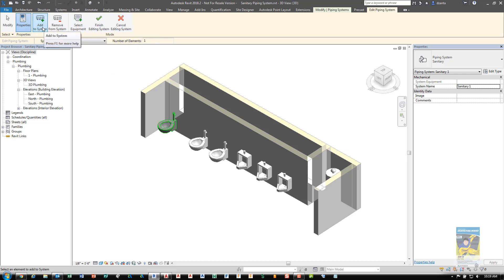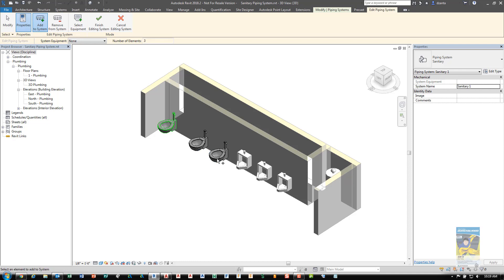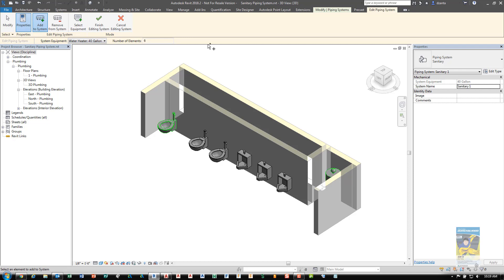By default, Add to System is turned on, letting you know I need to add other content. You can individually select other equipment or do a window crossing to tell the software these are all the components that make up the system. When you're finished, you need to tell the system what is the main equipment that it needs to tie back to. In this case, we'll choose the water heater. When you're finished specifying the design of the system and defining what it is, click Finish Editing System.